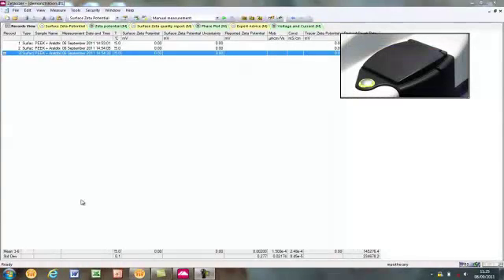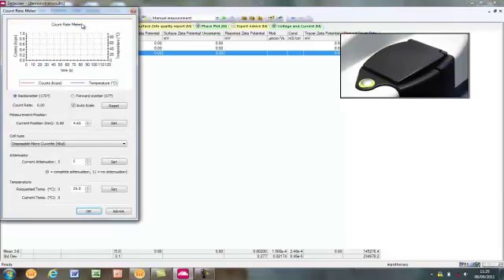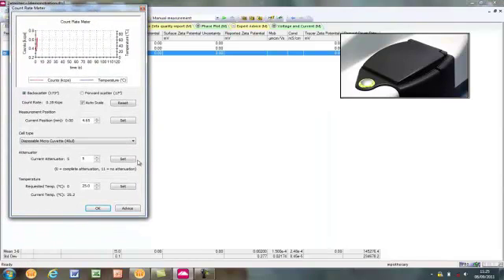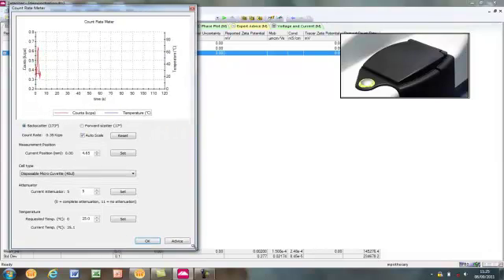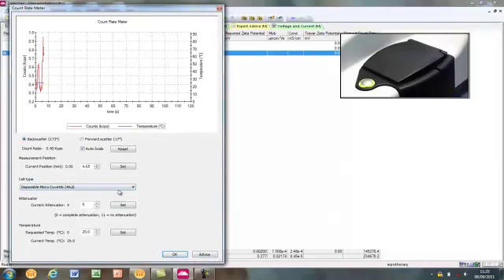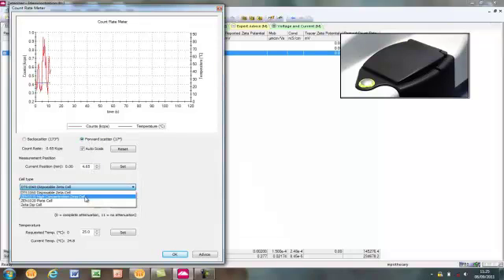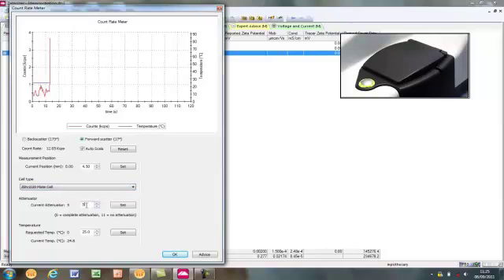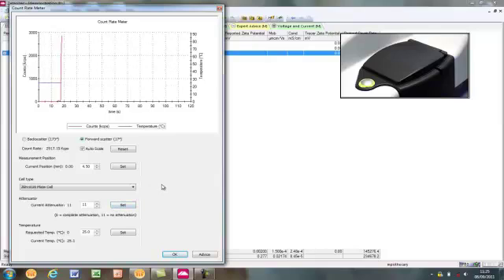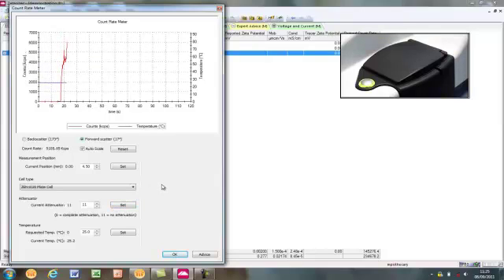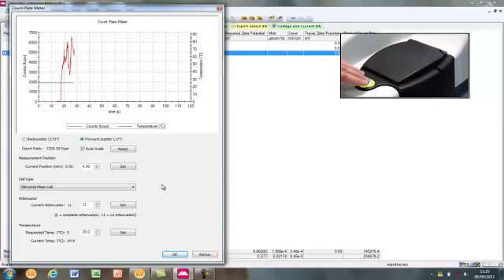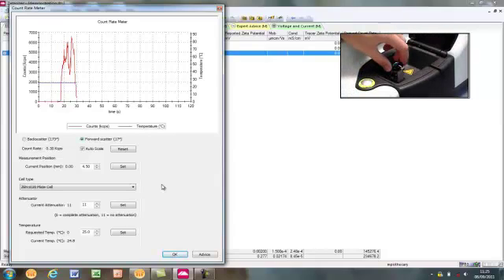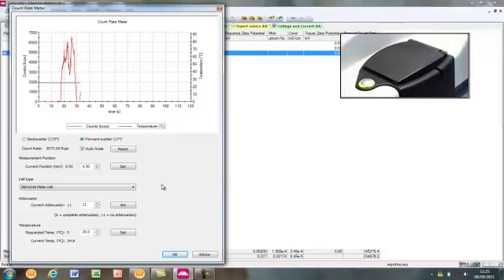The second zeroing step is a fine zeroing performed using the count rate meter in the zetasizer software. Open the count rate meter in the software under the tools menu. Select the forward measurement angle and set the cell type to Zen 1020 plate cell. Set the attenuator to 11 and monitor the count rate. If the laser is not covered, the count rate meter should be seeing a significant level of scattered light, in this case of the order of a few thousand kilocounts. Open the lid, turn the cell cap clockwise 45 degrees and close the lid, then monitor the count rate again.